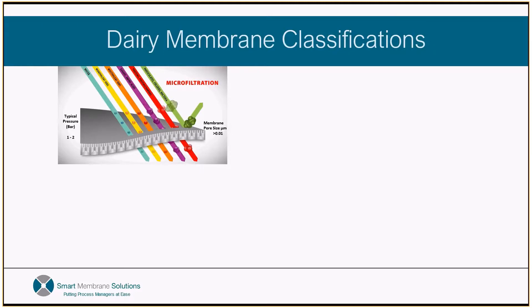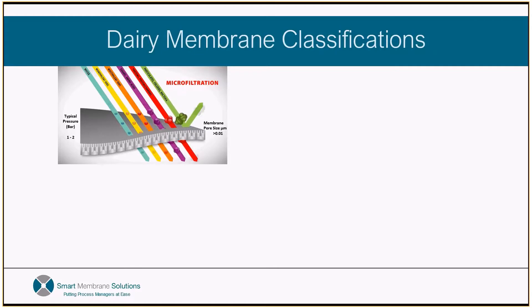First up, we have microfiltration. Microfiltration has the largest membrane pore size used within the industry. MF typically allows particles greater than 0.2 microns to be rejected by the membrane. Due to the open pore structure, system pressures within an MF plant to drive the separation process and extract permeate are low, typically in the 1 to 2 bar range, which is 15 to 30 psi.